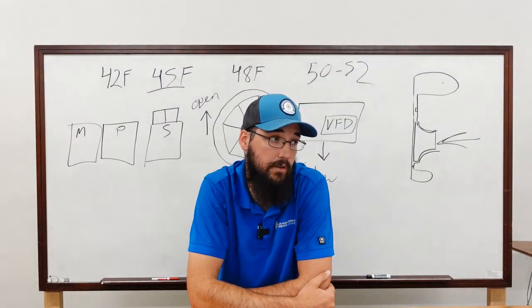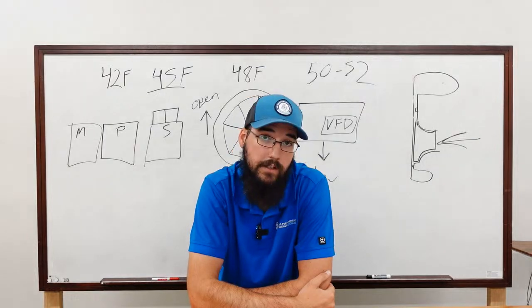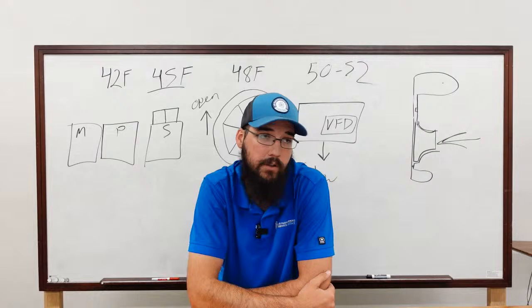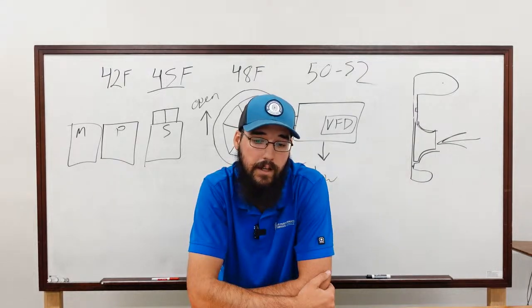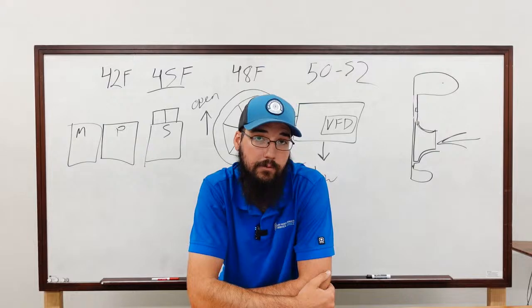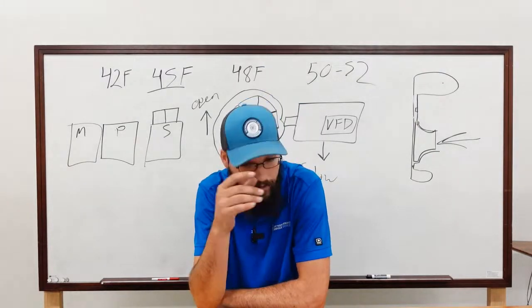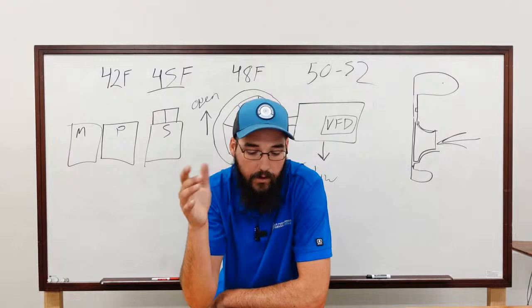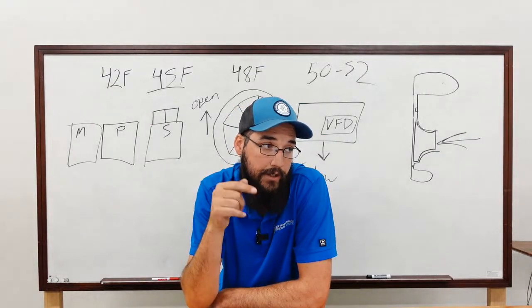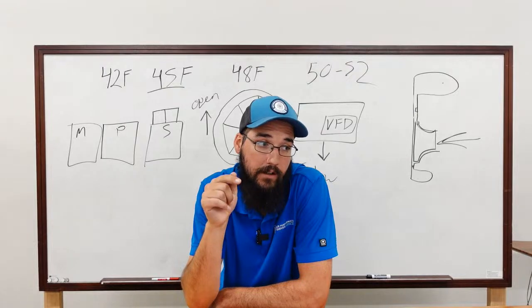All right, so you walk up, chillers got a surge. You're going to walk up to the display. You're going to see on that display that, one, you're probably not maintaining chill water set point because of the surging. It can't pull it down. But you're also going to see that your condenser water is really high. We're talking upper 80s, 90 something degrees. It can get higher.